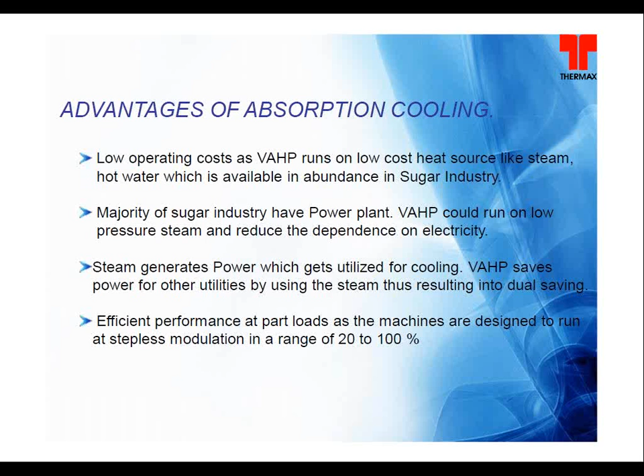Efficient performance at part loads, as the machines are designed to run at stepless modulation in the range of 20 to 100%. What we want to say is that the machine can take load up to 20% of its actual capacity, and with a VFD attached to the absorbent pump, the part load efficiency down to 50 to 60% will be more than the 100% efficiency.